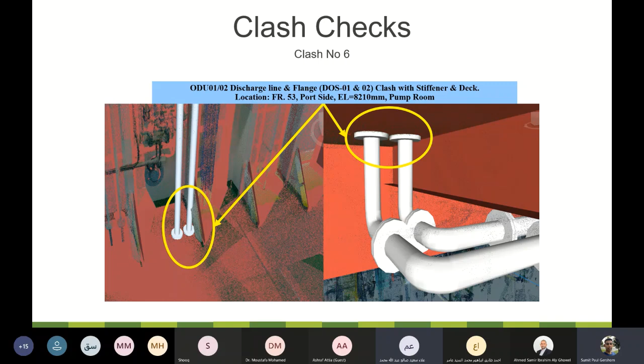Then the clash check, we still have a discharge line clashing with existing piping. This is one of the most tedious or critical issues we see on board the vessel. Clashes with stiffeners can be avoided, you just have to reroute the new piping, but the most common and critical issue is new pipes clashing with old pipes.